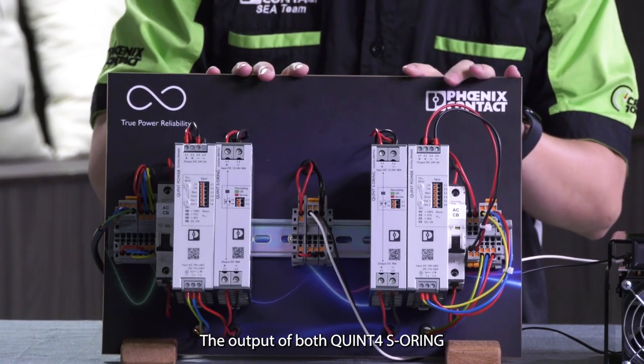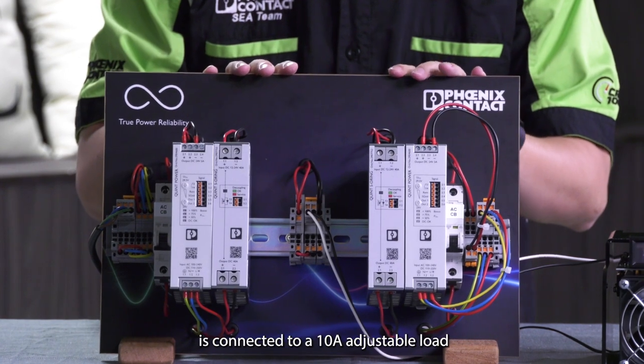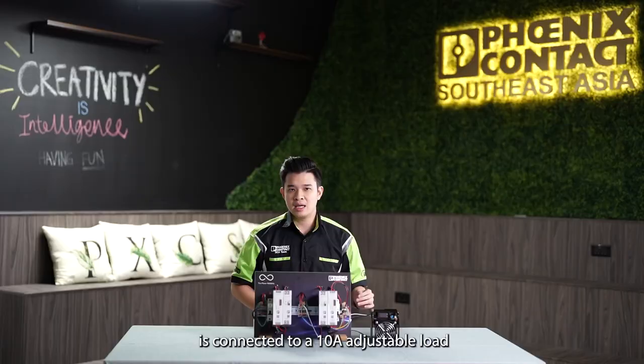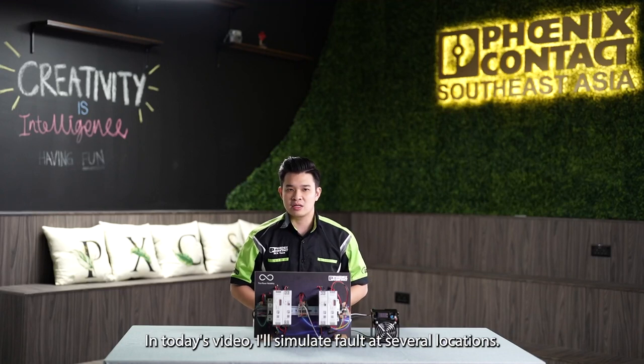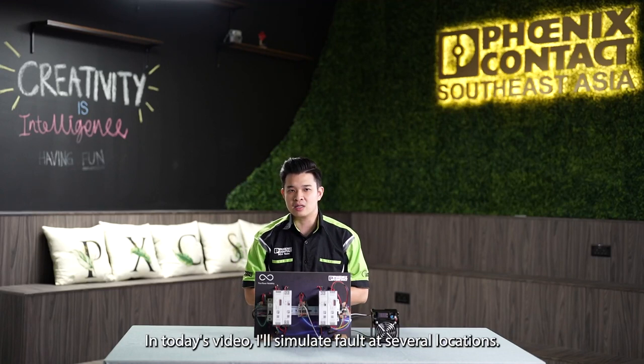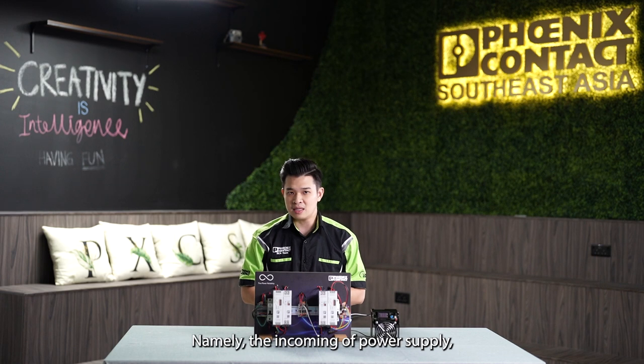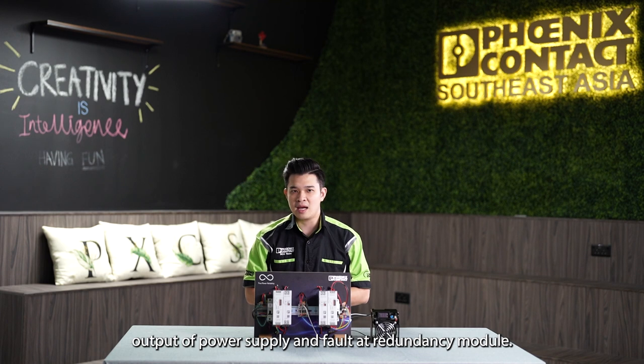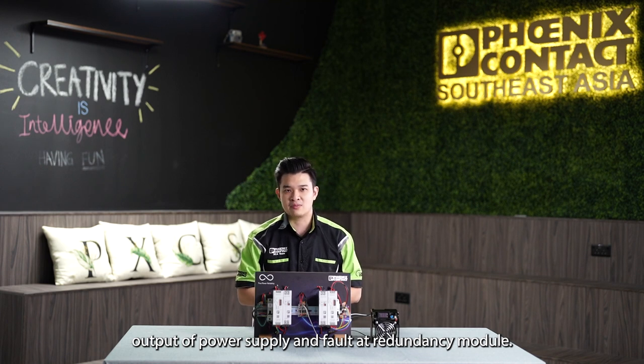The output of the QUINT4 S-ORING is connected to a 10A adjustable load. In today's video, I will simulate faults at several locations — namely the incoming of the power supply, the output of the power supply, and a fault at the redundancy module.